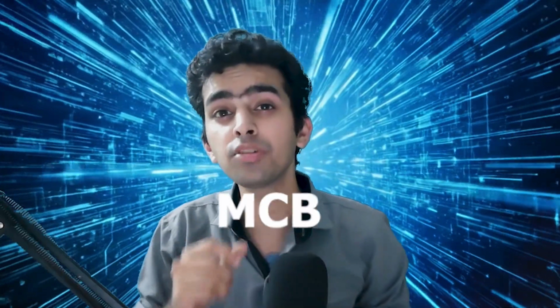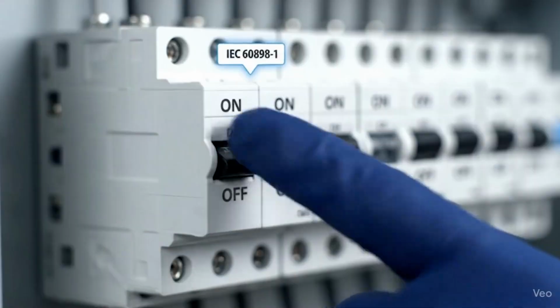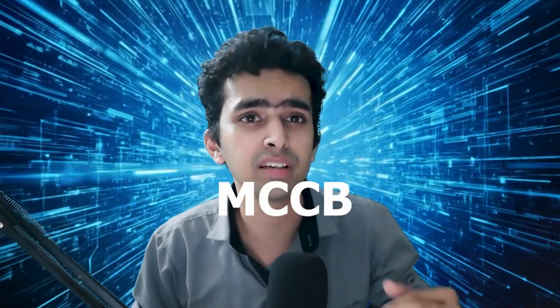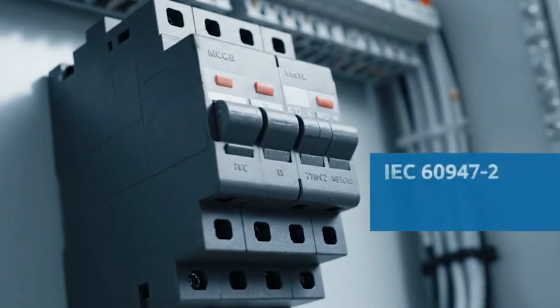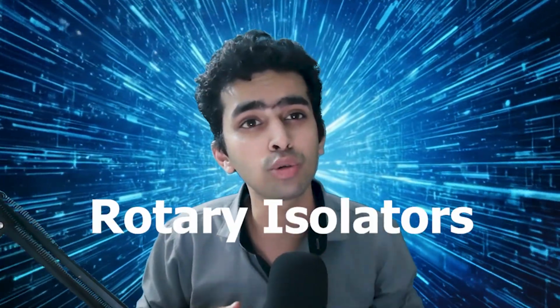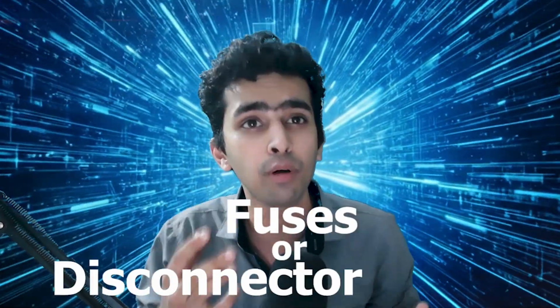And here is what we can actually use for our source isolation. MCBs, miniature circuit breakers, for overcurrent protection of voltage input lines. Next one is MCCBs for high current protection in large installations. Third is rotary isolators or load break switches for safe manual disconnection during servicing. And fourth one is fuses or disconnect blocks as backup source protection. Each source should have its own isolator or breaker, clearly labeled. This helps during troubleshooting or calibration, so you can cut off just one source without shutting down the entire plant.